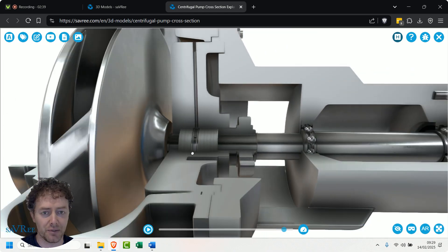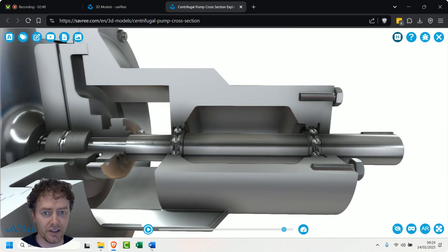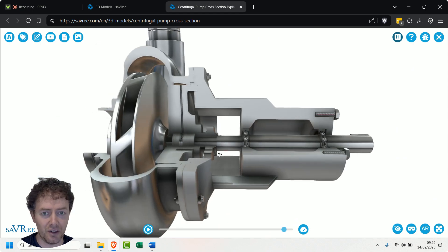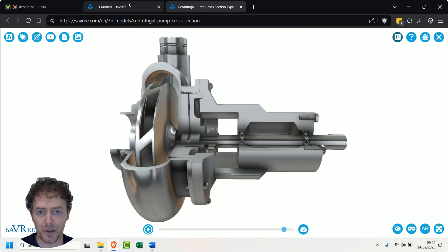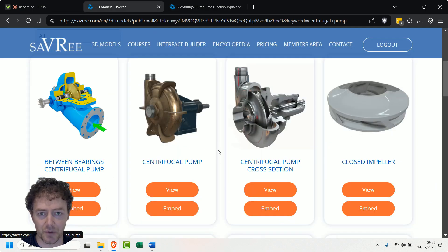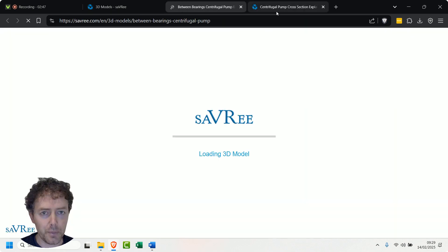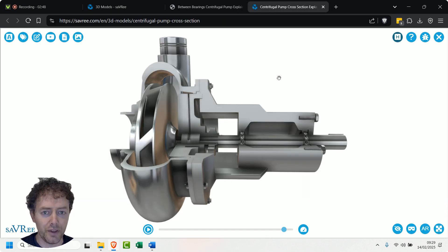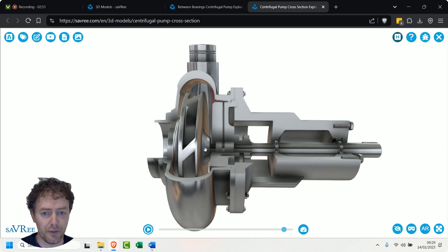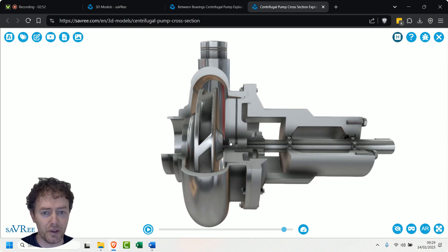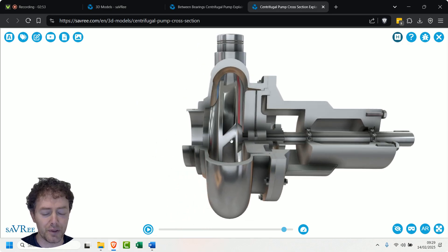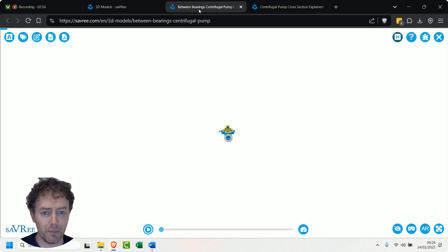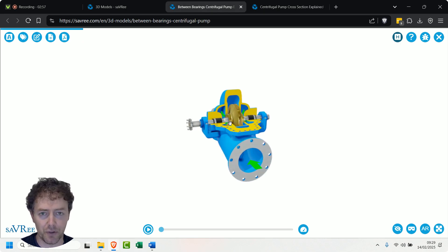So with that design, let me pull up a different one here because I just want to show you this. With the design that's overhung, there's only one other option you can really have, and that's where you support the impeller from both sides. And when you do that, it becomes a between bearings centrifugal pump.